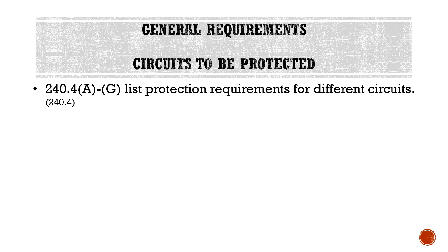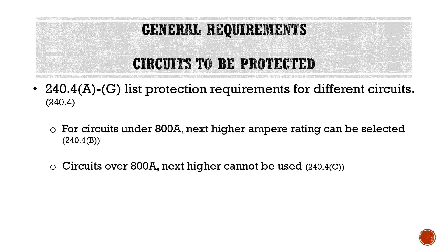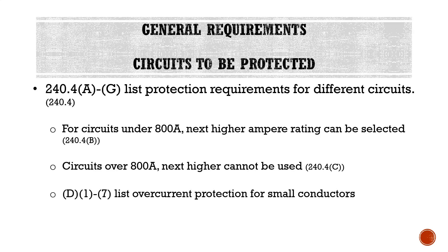Looking at our general requirements, we have a list of circuits that must be protected. Section 240.4 A through G lists protection requirements for different circuits. For circuits under 800 amps, the next higher ampere rating can be selected. For circuits over 800 amps, the next higher cannot be used. Section 240.4 D1 through 7 lists overcurrent protection requirements for small conductors. The most important concept here is this distinction between circuits under 800 amps and circuits over 800 amps.